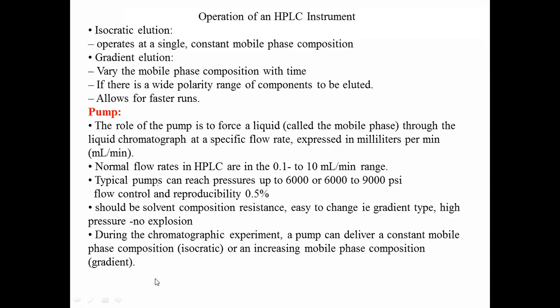So the function of the pumps, their pressure, flow rate, and the material used for the construction of the pumps are very important points. The pumps should be resistant to the solvent compositions, easy to change between the different elution techniques, isocratic and gradient, and there should not be any hazard with the high pressure.